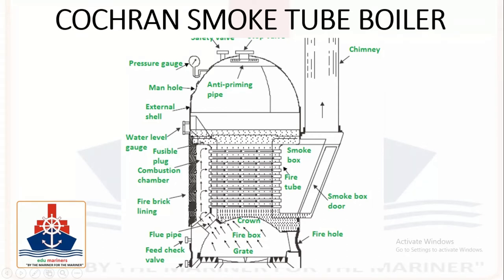Here refractory material is fitted on the combustion chamber — on this side of the combustion chamber, and on the floor and sides of the furnace — to safeguard the boiler shell from overheating.